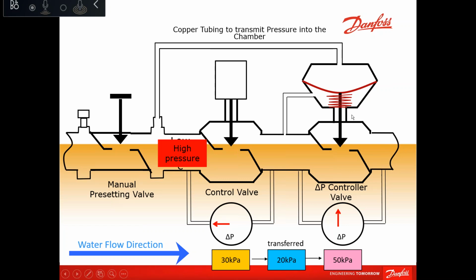The reason why we're doing this: the differential pressure controller will open and close based on the system pressure change. Why are we doing that? To leave the control part to only open and close based on the temperature, the area or room temperature change. So I'm only controlling this modulating valve to respond to my load demand. Then the control valve will be able to open at 5–10%. If I have 1,000 valves like this, and every valve can open up to 10% instead of the two-way, which can never go less than 50%, we are saving 40% of the pumped water, which we will see in the next slide. So this is the general concept of a PICV.